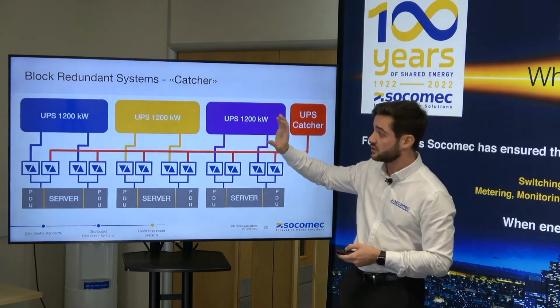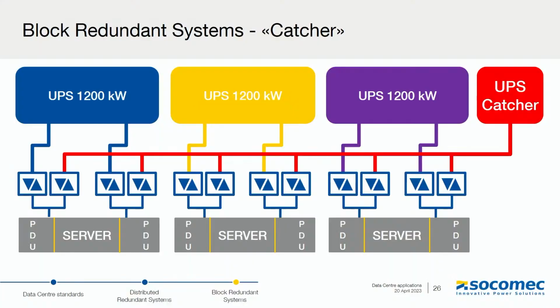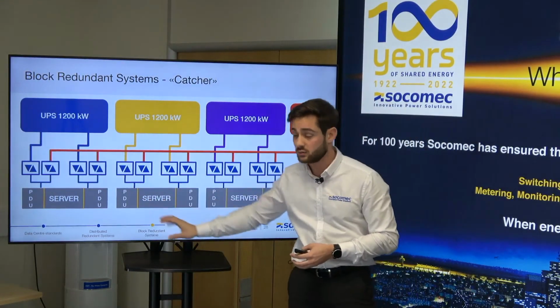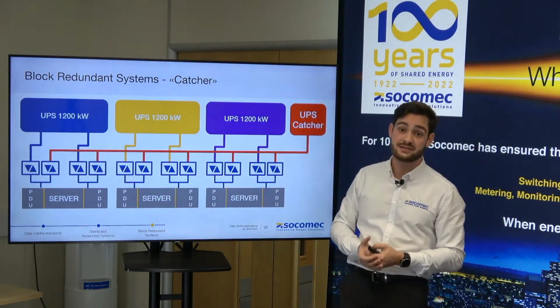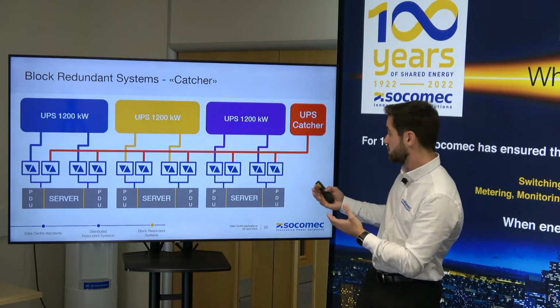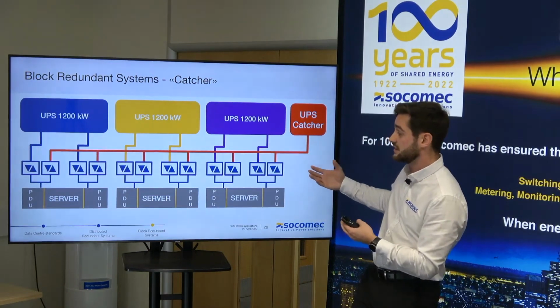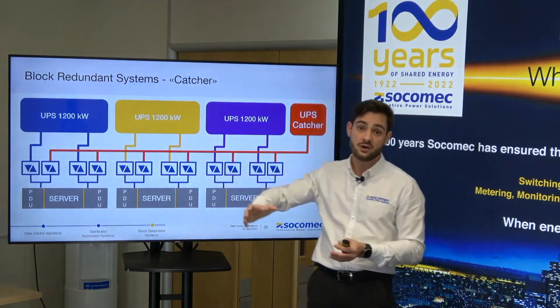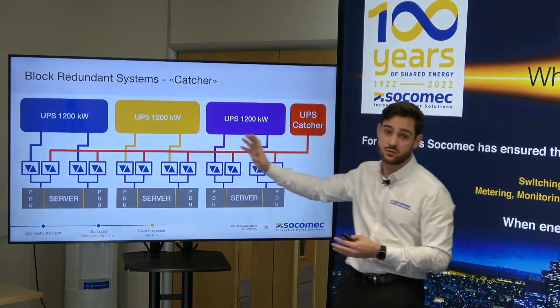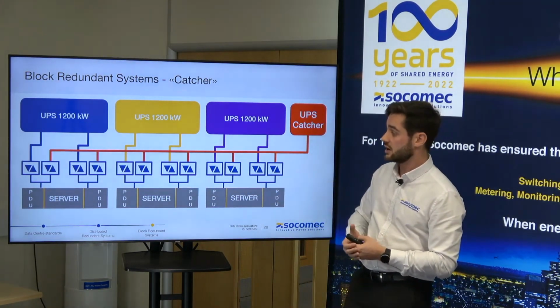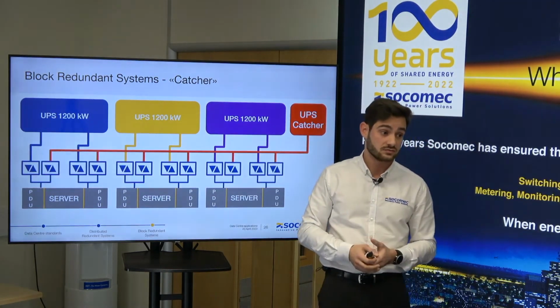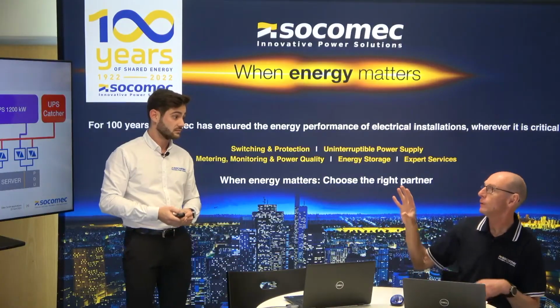In that specific case, we've got 3 UPS systems, each rated at 1200 kilowatts. But as you can see, the UPS catcher system is feeding all the alternative sources of the STS systems. So it means that it needs to cover the overall load, which is in this specific case 3.6 megawatts. So that's the purpose of the UPS catcher, and basically if you've got any failure, then you can rely on the STS to switch onto this UPS catcher. So there is a good point for maintenance as well. Yeah, and obviously you've got a reduced footprint because your redundant UPS now is just a single UPS catcher.